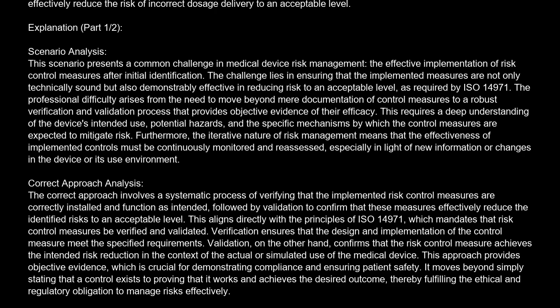14971. The professional difficulty arises from the need to move beyond mere documentation of control measures to a robust verification and validation process that provides objective evidence of their efficacy. This requires a deep understanding of the device's intended use, potential hazards, and the specific mechanisms by which the control measures are expected to mitigate risk. Furthermore, the iterative nature of risk management means that the effectiveness of implemented controls must be continuously monitored and reassessed, especially in light of new information or changes in the device or its use environment.